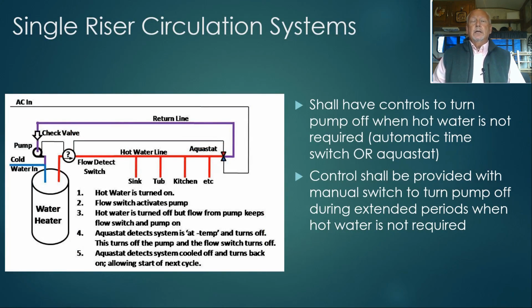So moving on for some additional changes in service water heating. The language around circulating water heating systems has been simplified, which is a helpful change. So if you have a single riser, simple circulation system with a pump and a recirculation line, you shall have controls to turn the pump off when the hot water is not required, either an automatic time switch or an aquastat. You don't need both.